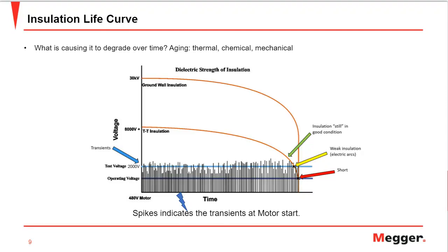This is the shape of the graph for every motor insulation. On the x-axis you see time, and on the y-axis you see the different types of voltage. So 30 kV, or around 28,000 V DC, is the ground-wall insulation we've seen in the previous slides. The 8,000 is the turn-to-turn. 2,000 is the test voltage. The blue line is the test voltage, 2,000 volts, which we usually do our high potential testing and surge testing on. And the purple line indicates the operating voltage of that motor.